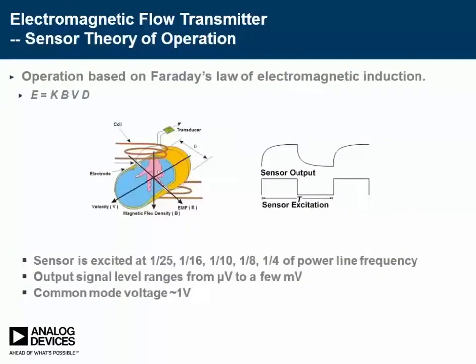Let's take a look at the theory of operation of the electromagnetic flow meters. The operation principle is based on Faraday's law of electromagnetic induction. It states that a voltage will be induced in a conductor moving through a magnetic field. The liquid serves as the conductor, and the magnetic field is created by energized coils outside the flow tube. The magnitude of the induced voltage is directly proportional to the velocity of the conductor, the diameter of the pipe, and the strength of the magnetic field.